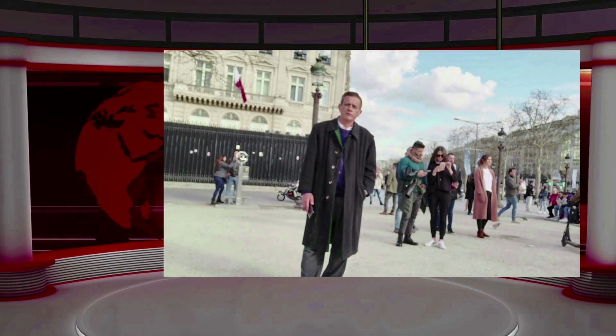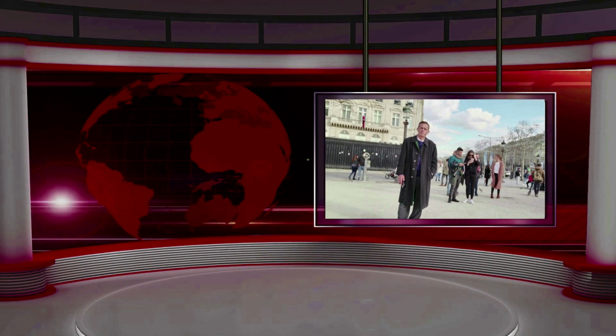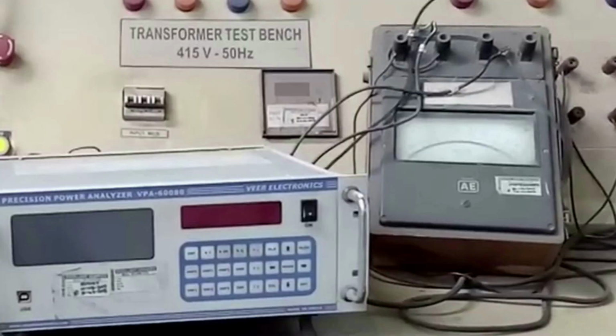We will be discussing these tests from the practical point of view, focusing on the physical meaning of these tests. We will be studying these tests one by one. For each test, we will define the test in simplified wording, mentioning the reasons to do such a test, the equipment used in this test, the connection diagram for the 3-phase distribution transformer, and you will see practical results taken from the factories and on site for these tests, and we will explain these results in a very simplified, practical way.